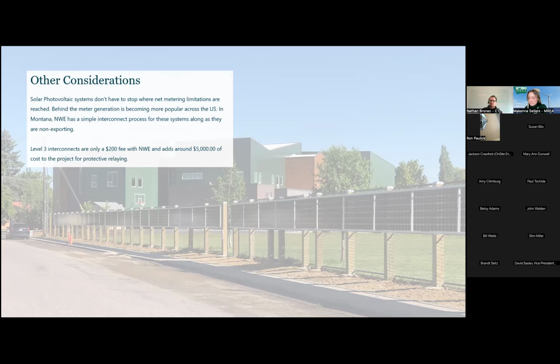It's a really common relay for utility applications. We use an SEL 751 relay, and that has its own basically PTs and CTs that are monitoring the building. When you set up those level 3 interconnects, we're required to have either a minimum import or minimum export amount, a slight buffer that NWE requires.